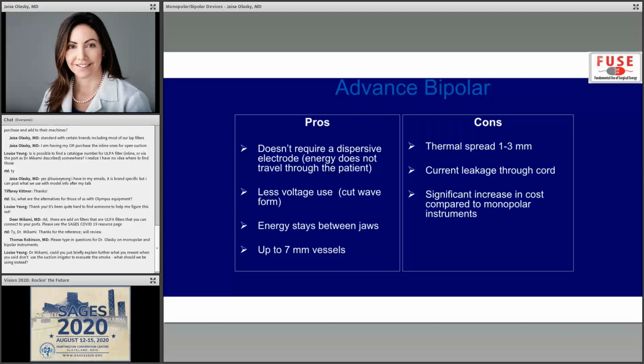Other cons, current leakage through cord, I mean, that's really more of a capacitive coupling issue that can happen with monopolar or bipolar instruments. And the cost increase. It depends on what surgery you're doing. If you're doing a surgery that's long and could have blood loss, then certainly that cost is offset by shorter OR time and shorter length of stay for the patient. If you're doing an appendectomy, it's a little bit hard to justify, depending on your math at your hospital. It may be hard to justify using an advanced bipolar instrument, though some hospitals do.